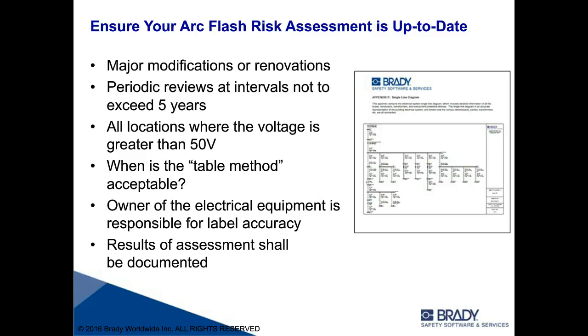In other words, the tables may only be used if the specific task being performed is listed in that table, and the system meets the listed criteria for the short circuit current and speed of response of the circuit protection. So if that task does not appear in the table, or the fault current or circuit breaker clearing time do not meet the criteria listed, that table cannot be used for those activities, and you would have to have the engineering analysis take place.